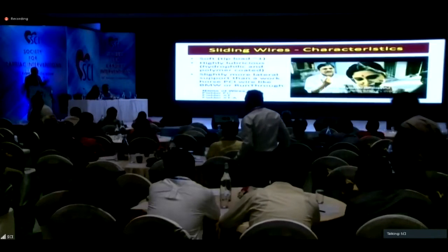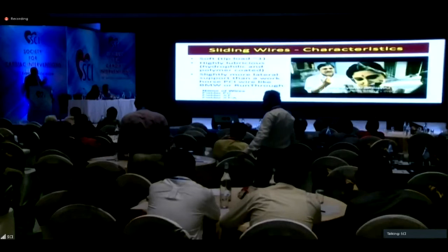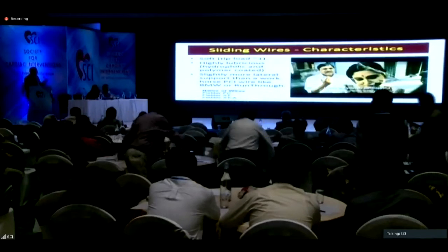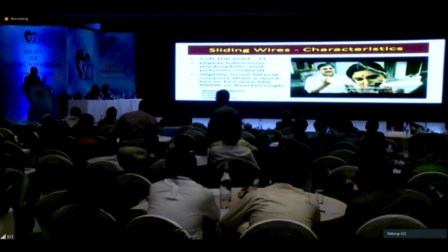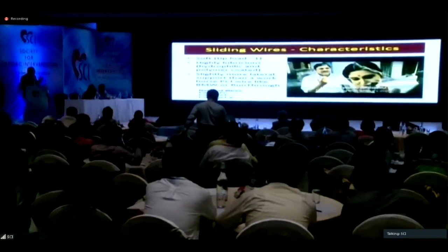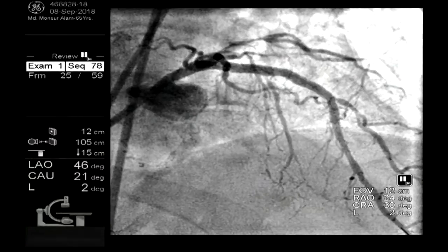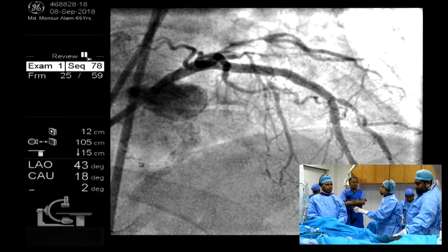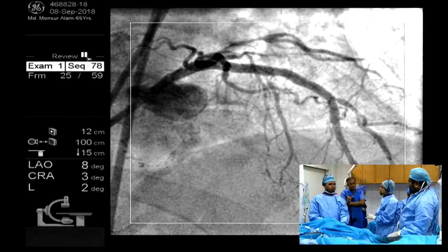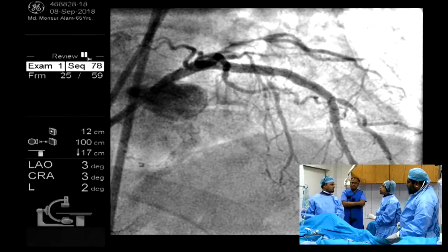Second important thing, because it has to go through a highly resistant area, it has to be highly lubricious. So even in a micro channel, you need a highly lubricious wire, probably polymer coated. And then lastly, what I said was that an important thing is to have a lateral support, because there is some resistance, so you have to overcome that resistance. So you need a lateral support. Some examples of these kinds of wires are Fielder FC, XT, and XTA, which is a specialized wire.